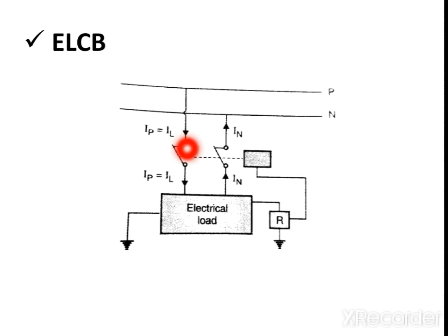So the magnitude of phase current and line current is equal, and there is no operation of this relay coil. Whenever a fault occurs or there is insulation failure, the phase current and line current are different. So there is a difference in voltage, and this different voltage is measured by this relay coil, and the relay will send the signal to the circuit breaker, and this will protect the human being from the electrical shock.